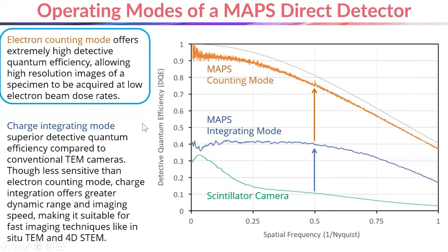Electron counting is a mode in which the MAPS detector is able to identify and count each electron incident on the sensor, so long as you operate the detector under suitable low-dose conditions. This counting mode can achieve quantum efficiencies approaching the theoretical maximum, which are enormously higher than those of scintillator coupled cameras, making electron counting MAPS detectors very useful for imaging specimens with minimal beam damage.